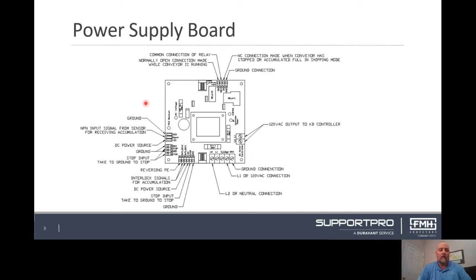There are several lights on this board that will allow you to visibly see the state of the board. The red light is illuminated when a stop signal is being received. This could come from a stop button or a photo-eye package stop if equipped.